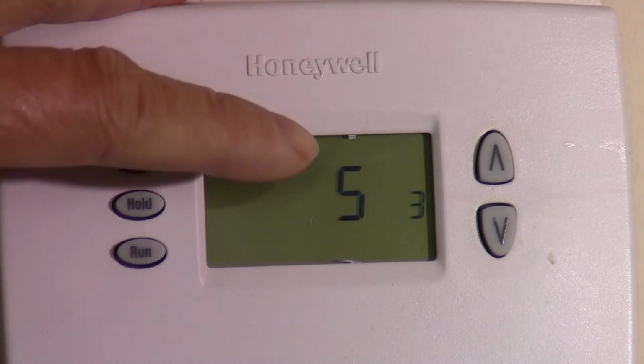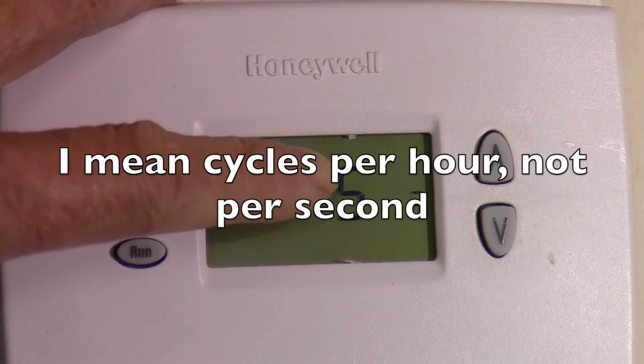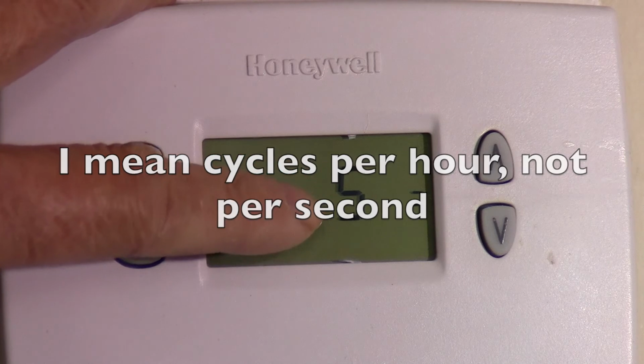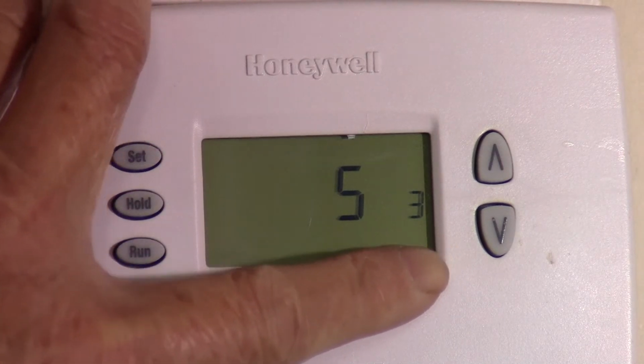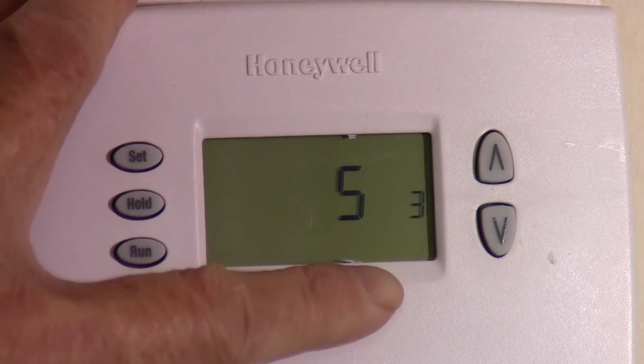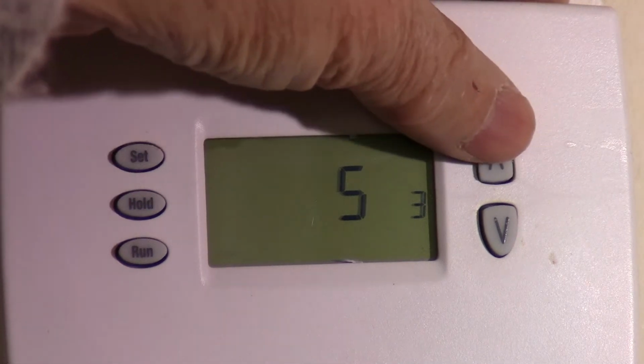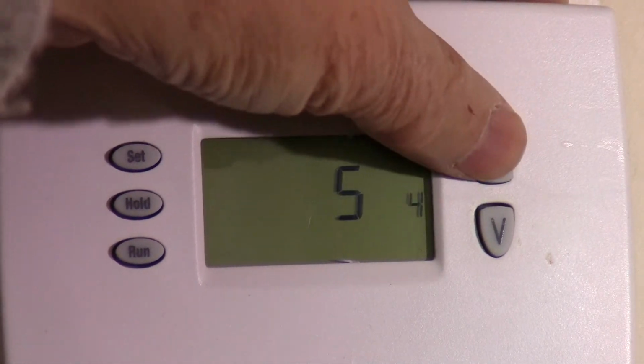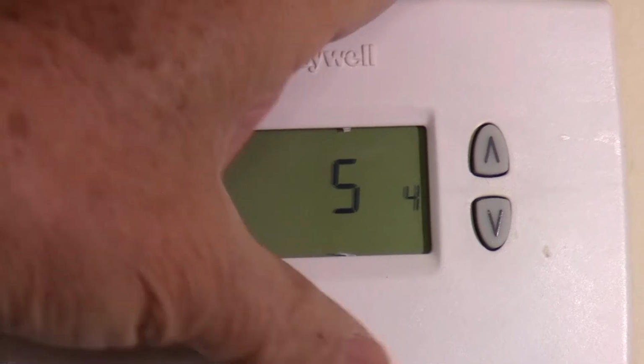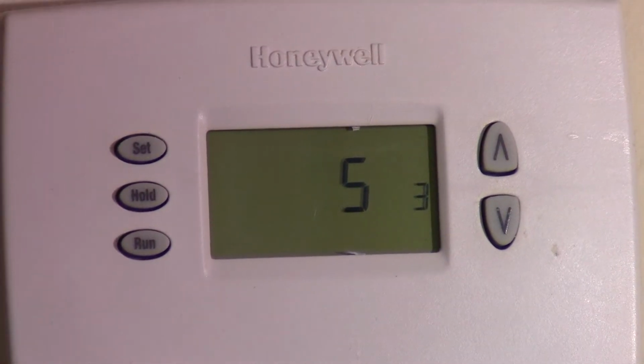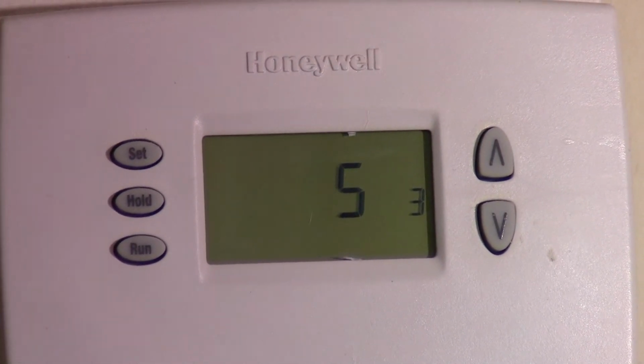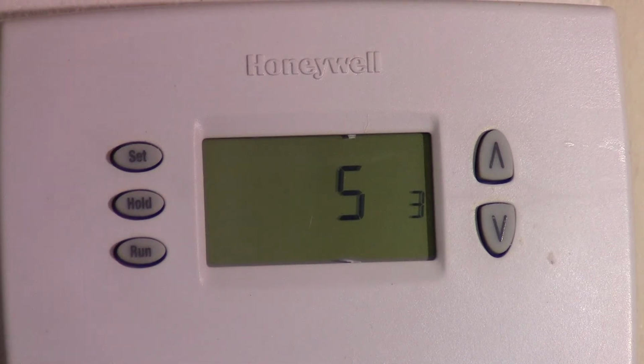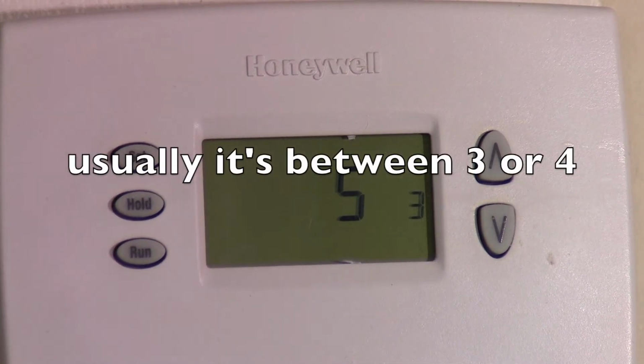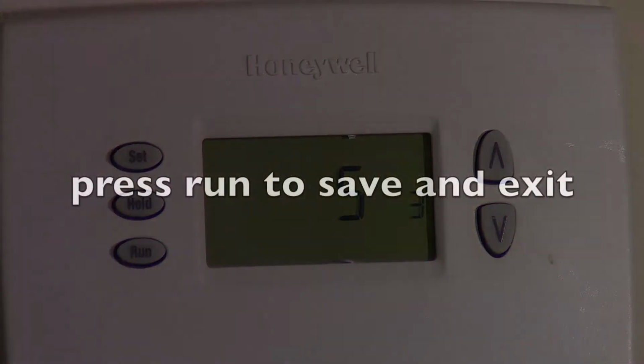The selection mode for cycles per hour is function number 5, and 3 is 3 cycles per hour, and you can change it to 4. I had it on 5 before, but that's not the recommended one. The recommended one for hot water is 3. So this is how it is set.